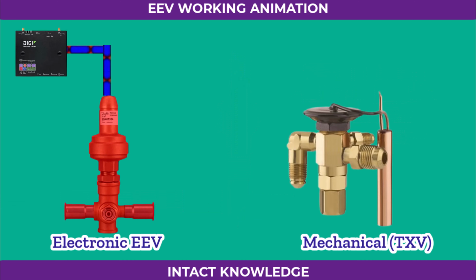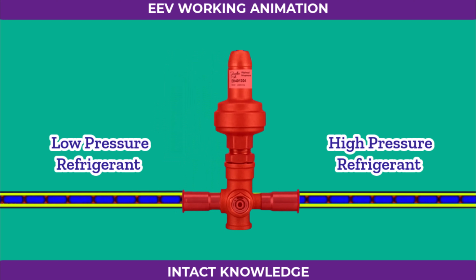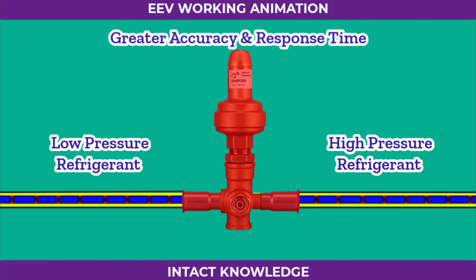Unlike the thermostatic expansion valve, which functions mechanically, the EEV works electronically by receiving input from sensors and control signals sent by the system's controller. Its purpose remains the same: to drop the refrigerant's pressure and control superheat at the evaporator outlet, but it does this with far greater accuracy and quicker response time.